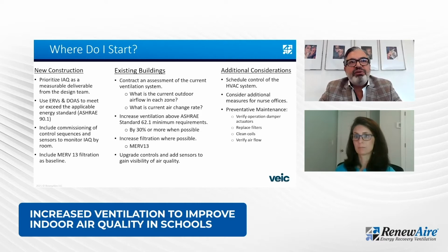Like I alluded to earlier, when you're talking about a school that may be 100 years old, that's just using hot water to heat the space with no ventilation, or even upgrading some of these systems that may have been designed for only 5 CFM per person, it becomes a little bit more challenging. Challenging because, yes, your mechanical systems can't handle it, but even more challenging because where do you put these energy recovery ventilators, because there isn't any space on the roof or on the outside of the building. So you're trying to find that really expensive and hard to find real estate within the building walls.